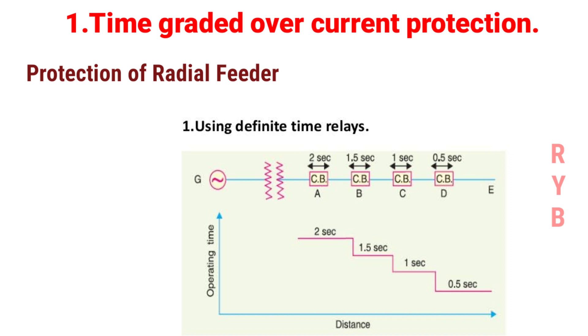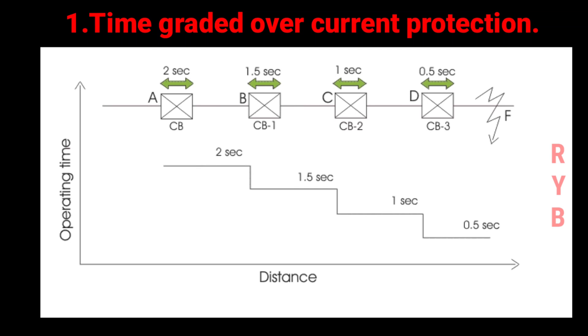In the definite time relay protection scheme, the total line is divided into different sections and each section is provided with a definite time relay. A definite time relay operates after a specific preset time period whenever a fault occurs in the feeder or transmission line — after that set time, it will trip the circuit breaker.